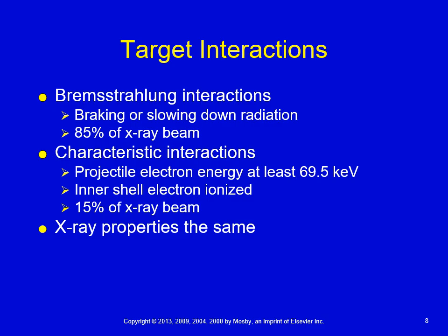As we are taking the patient's X-rays, about 99% of the electron interactions will produce heat, and only 1% of those interactions will result in X-rays. So as a result, eventually in this chapter, we'll learn about heat units.